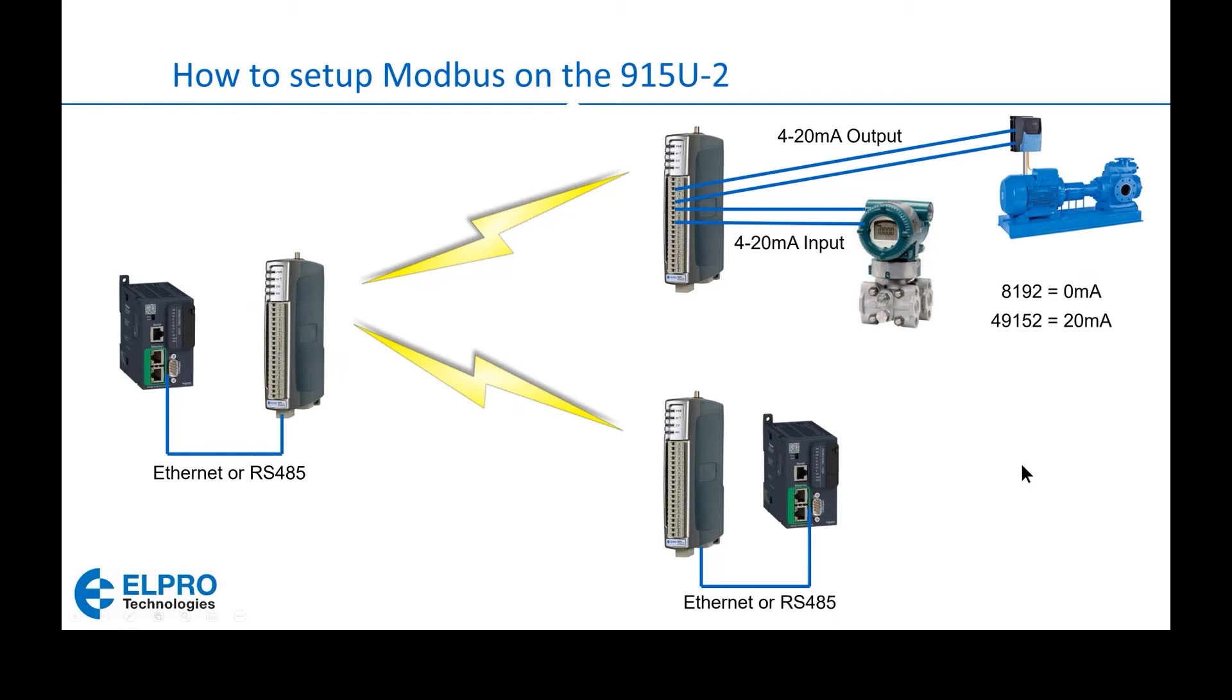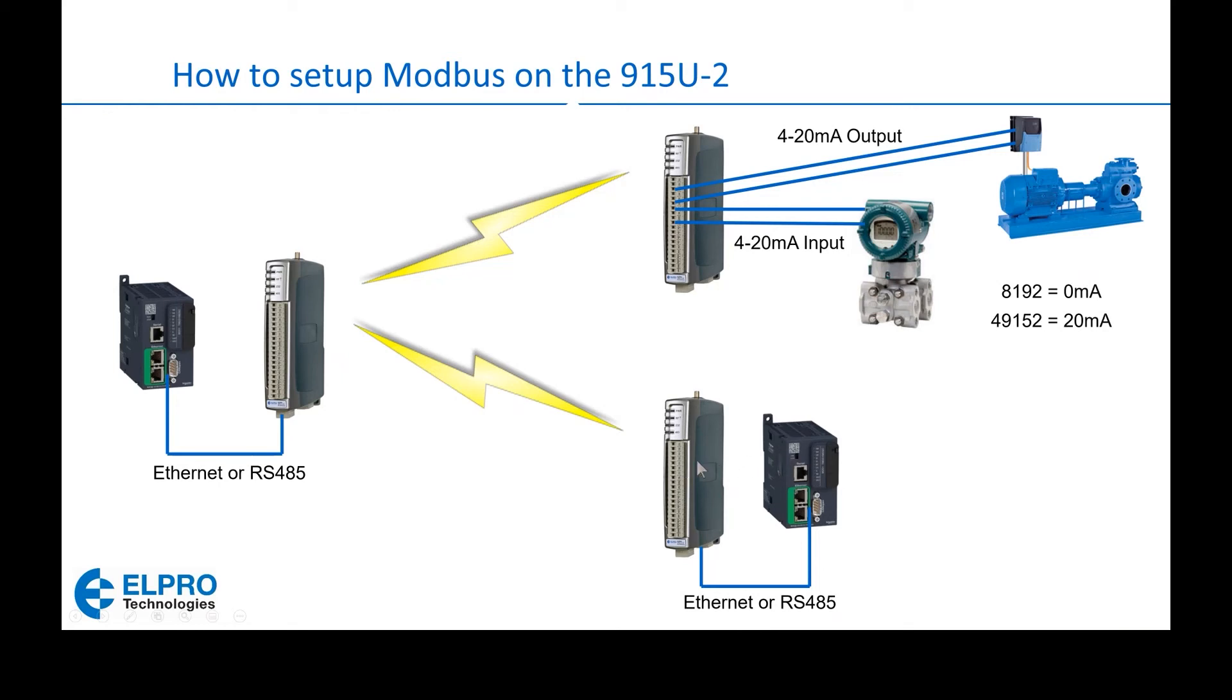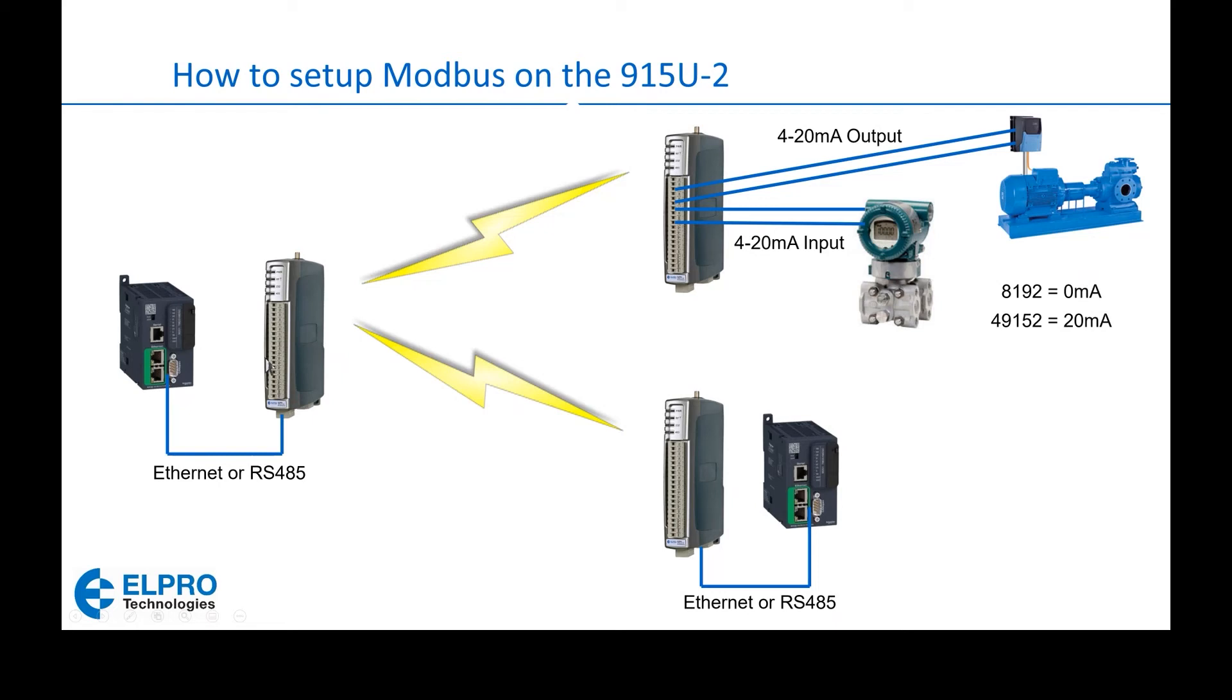And at other remote sites we could also have another Modbus master slave setup. Now to be clear, to transfer data from this PLC over to this PLC is a three-step process. The first step is to set up the Modbus master slave between the remote radio and this remote PLC. The second step is to create wireless Modbus mappings going from this remote radio back to the master radio. And lastly, the third step is to create a Modbus master slave setup between the master PLC and this master radio.